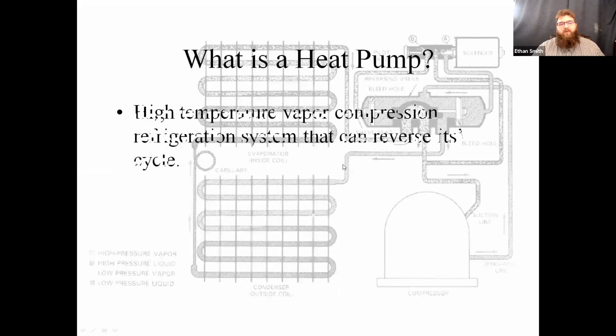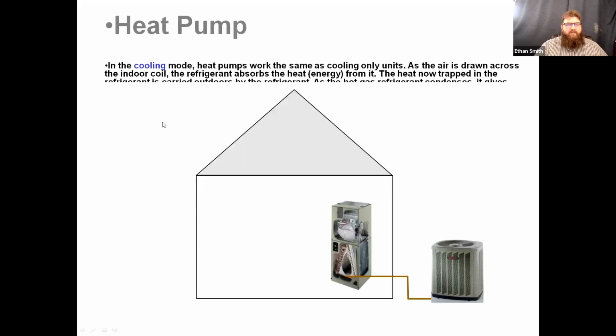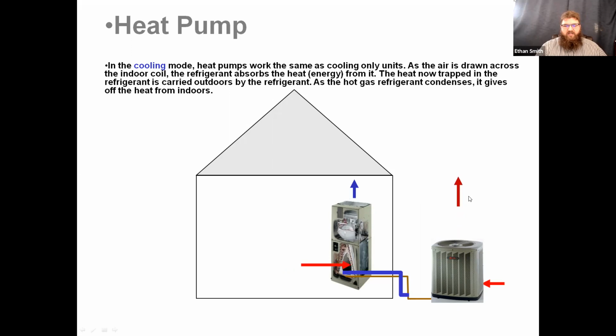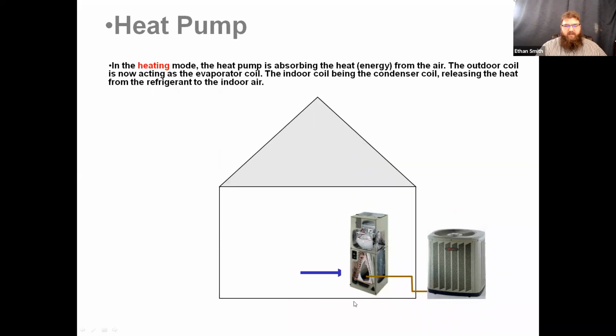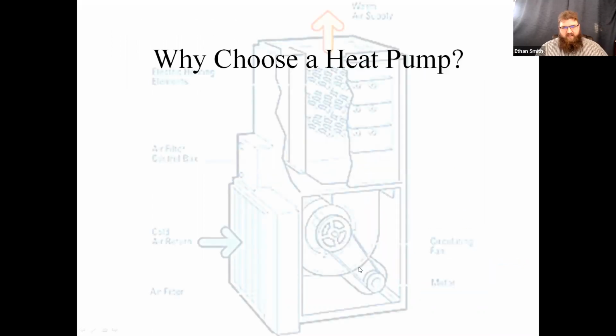So what is a heat pump? This is via our good friend Webster. It's a high temperature vapor compression refrigeration system that can reverse its cycle. So basically in cooling mode, we're used to seeing this. We've got an indoor unit with a coil and a blower, and we take heat from the indoor airflow and reject it through the suction line out to the outdoor unit, where we reject it to the outside. This causes our air coming into the unit to be cooled as it goes into the house. In heating mode, we do exactly the opposite. We're absorbing heat from the outside air, transporting it through the line set into the indoor coil, and we're using that indoor coil to reject heat to the inside space.